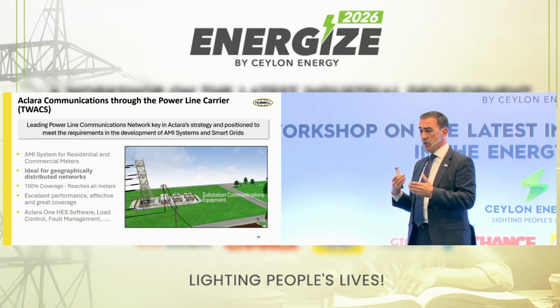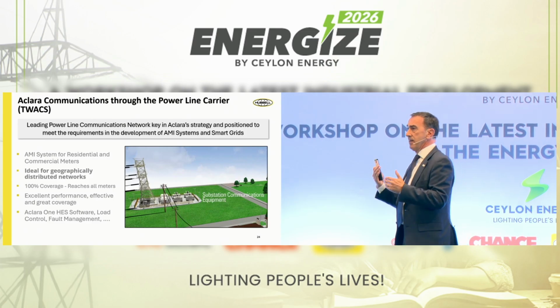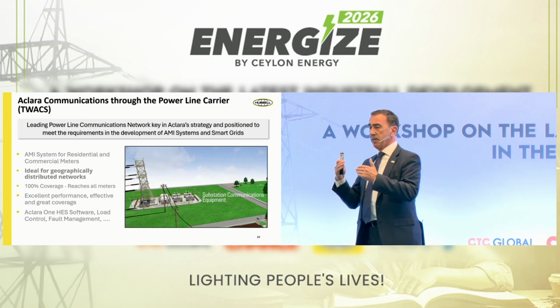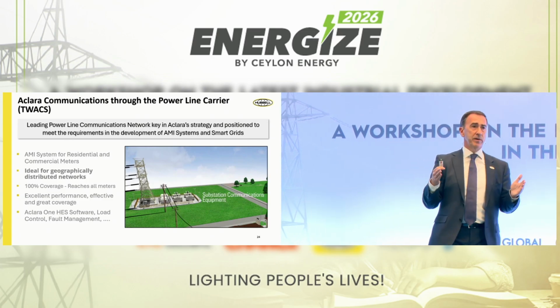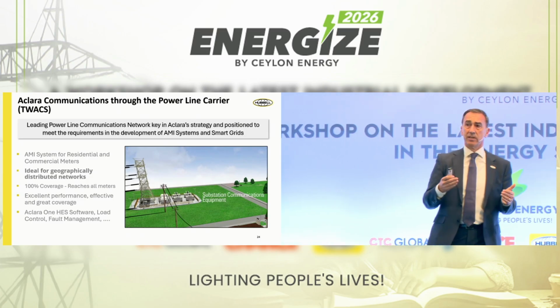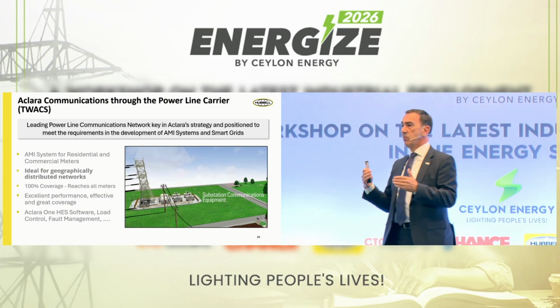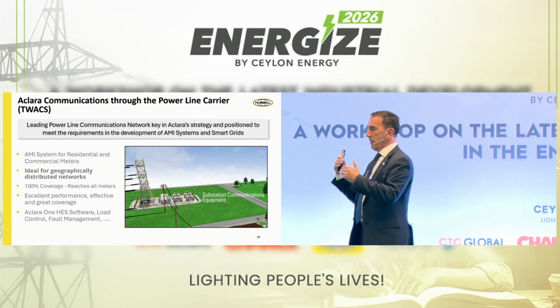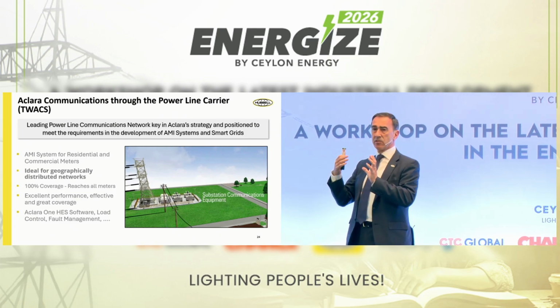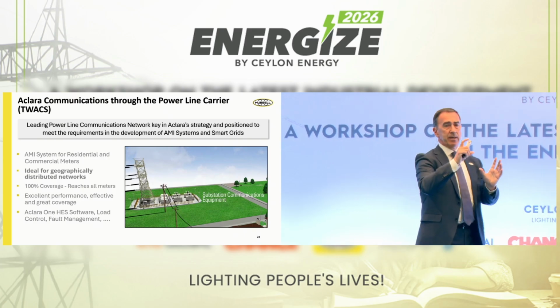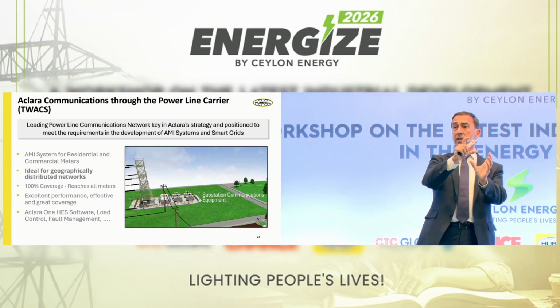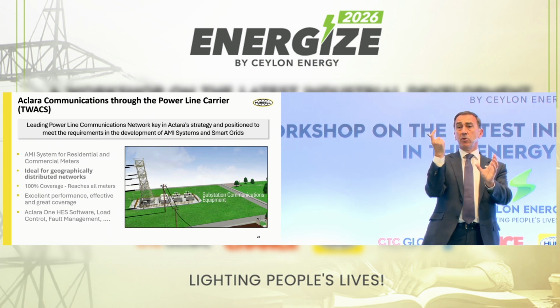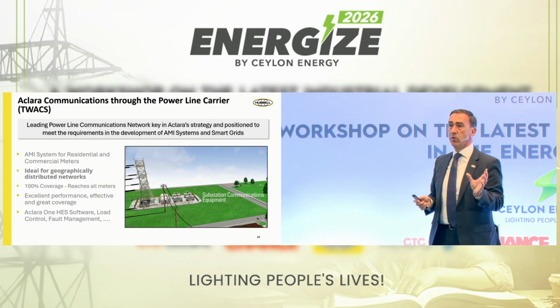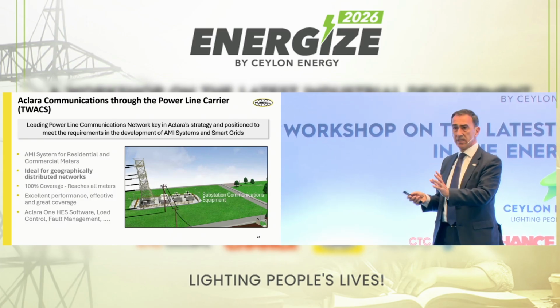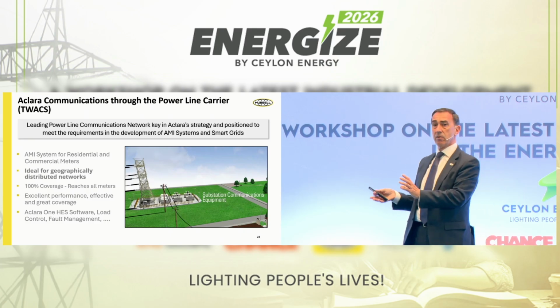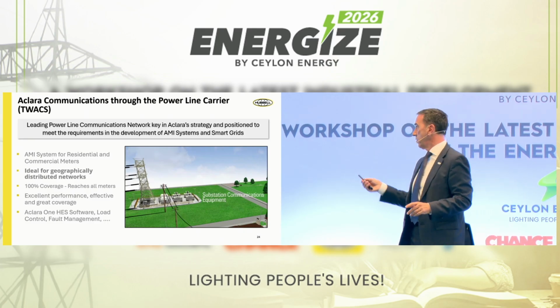On top of that, there's additional value: you may not have cellular coverage in some areas now, but may get it shortly. So what can you do? We've done this with some customers, where a customer has a meter with TWACS communication, and can go replace the module and put a new one on top of it. So you're converting a module that was working in TWACS for several years, and now that you have cellular coverage, you can replace it and put a new module on top of it.